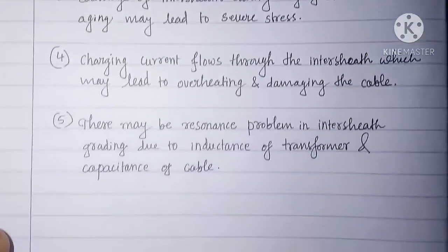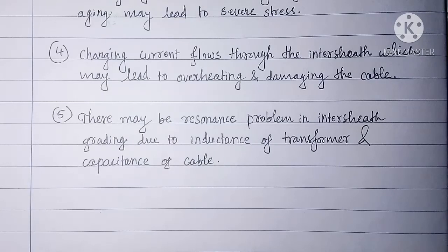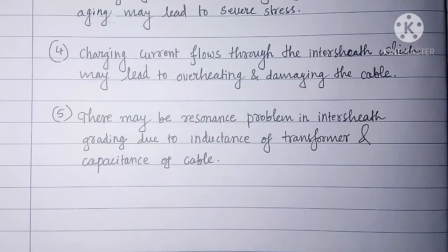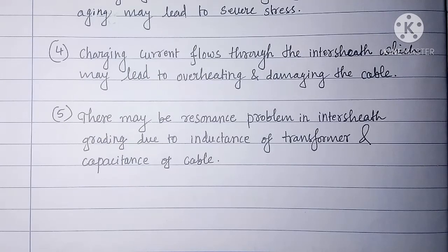I hope you all have studied resonance occurs when inductive reactance in a circuit becomes equal to capacitive reactance, and at that time impedance of the circuit will be equal to only resistance. That means impedance decreases drastically, thereby increasing the leakage current, which may once again lead to the overheating and damaging of the cable.